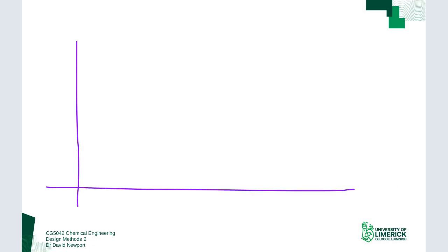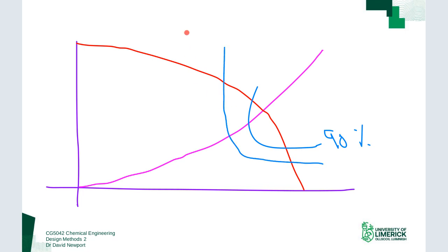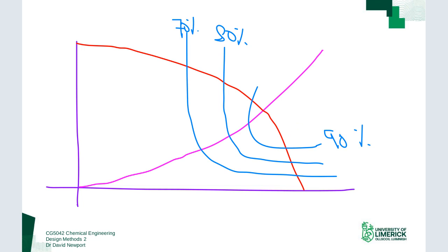The operating point is important because there is an efficiency associated with the ability of a pump to move the fluid. If we sketch a pump curve, typically in a central region we would have a high efficiency — around 90%. As we move off this region, efficiency decreases: 80%, 70%, and so on. The best efficiency point is the region where the efficiency of the pump is maximum, and you want to get your pump onto that sweet spot because that is where it is designed to operate.